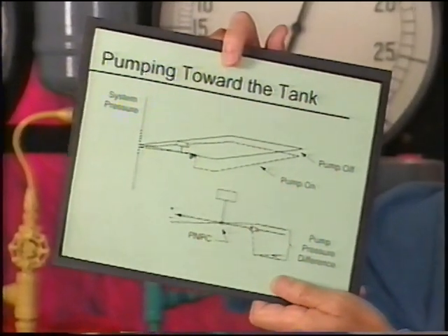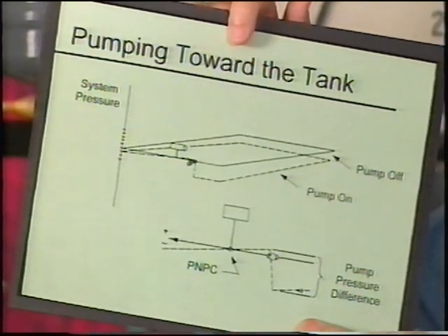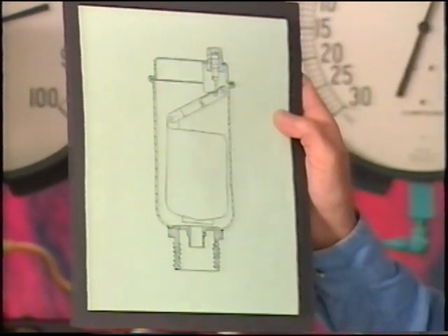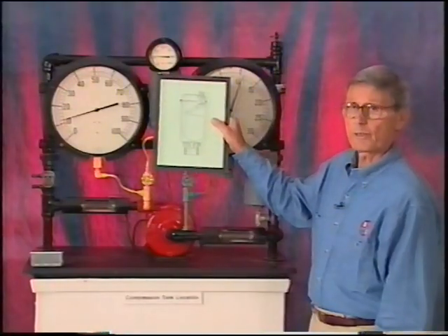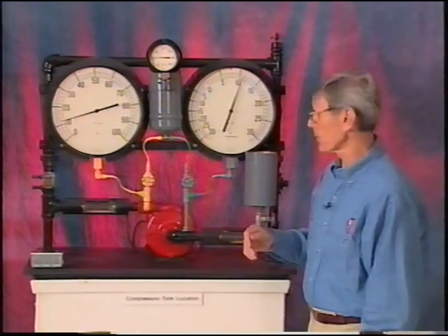If the head of the pump is greater than the non-operating pressure in the system, at least part of the piping system will operate in a vacuum. An automatic air vent installed in an area with a negative pressure will suck air into the system. Not a welcome occurrence. Since seeing is believing, hopefully the following demonstration will solidify your thinking on this problem.